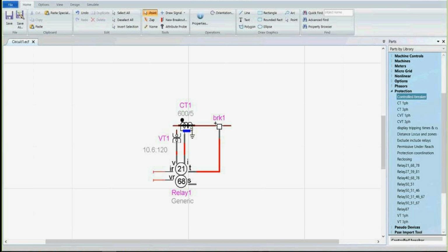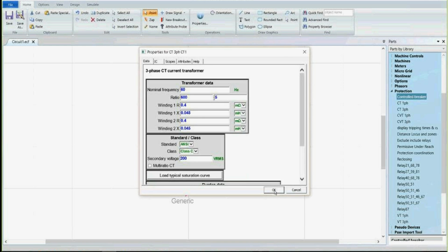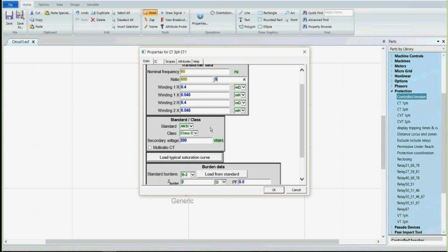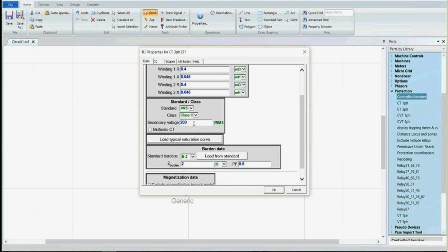Okay, so let's go quickly through those models of CTs and VTs. So very classic, it's kind of the same model as the regular transformers in EMTP. You input the nominal frequency, the ratio, the current at the primary and at the secondary, then the resistance of the current transformer, the reactance as well, primary, secondary.